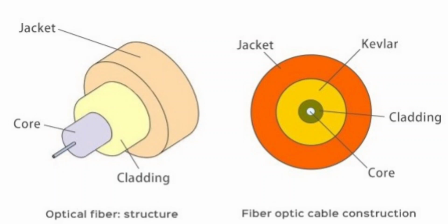But the other notable difference is because the outside cable has that PVC rigid material on the outer jacket, it is highly toxic if burned and is therefore not rated for indoor use. The NEC actually has a code that is supposed to prevent you from running it more than 50 foot inside of a facility. There are some exceptions to that.